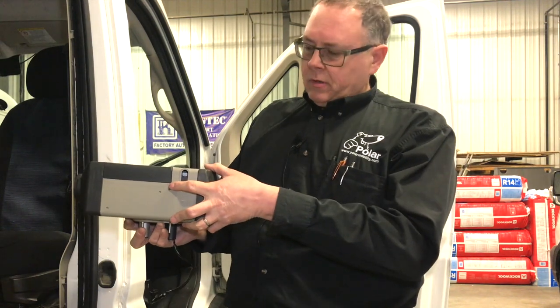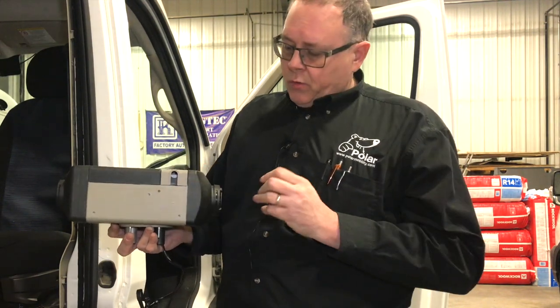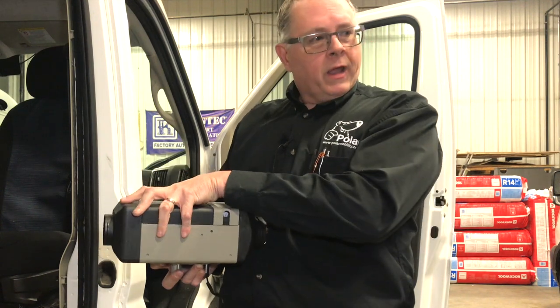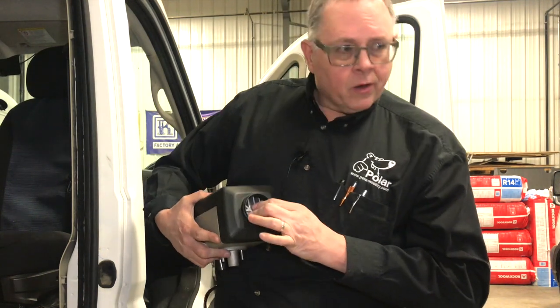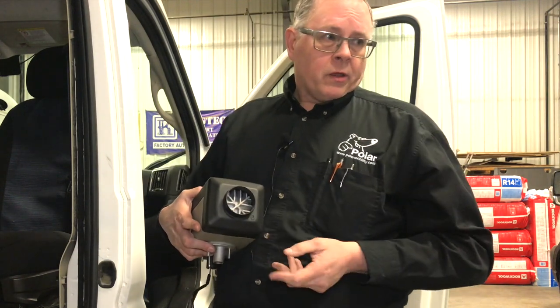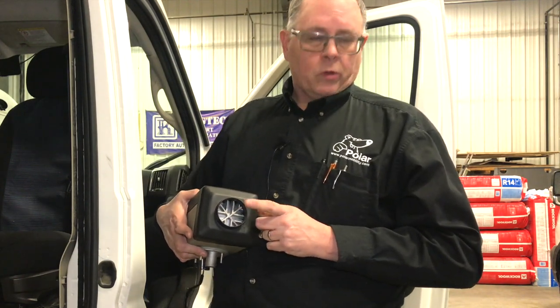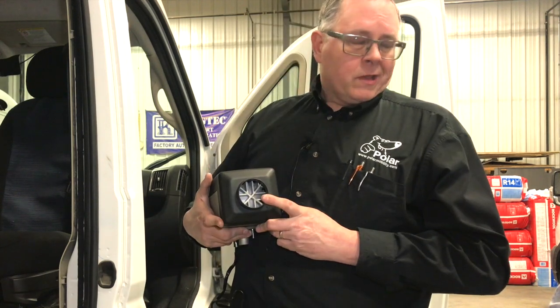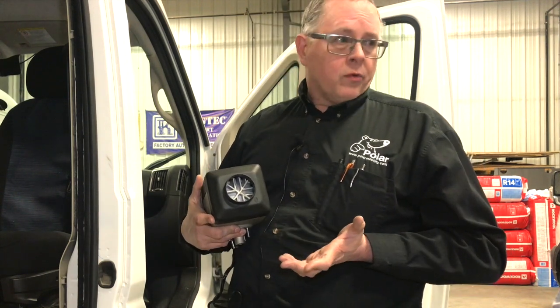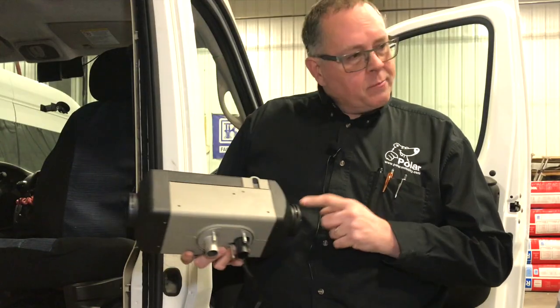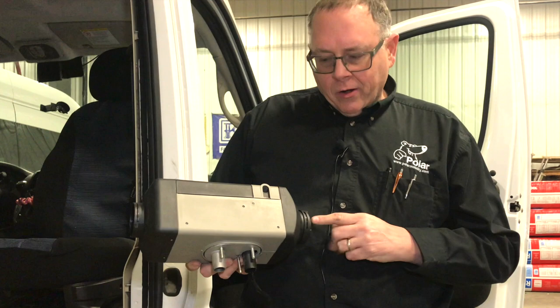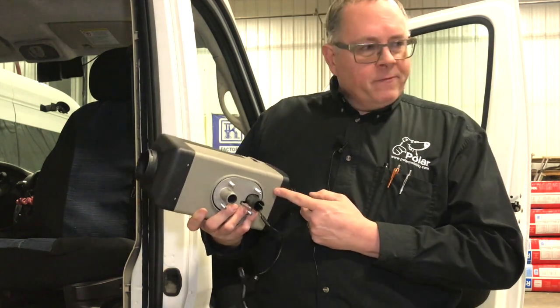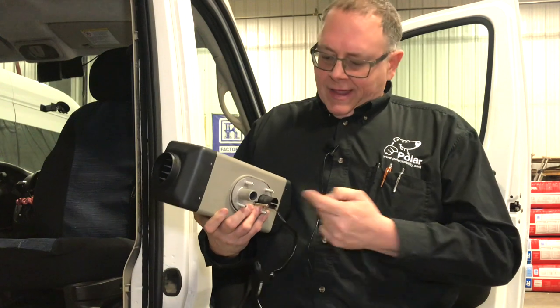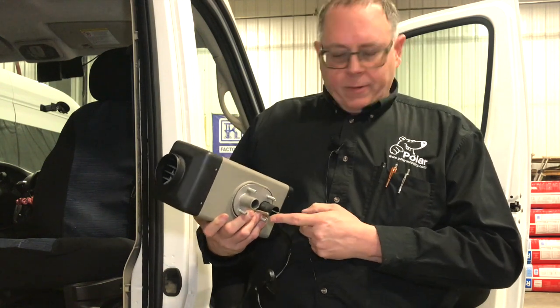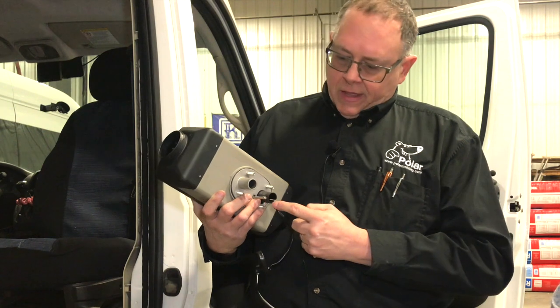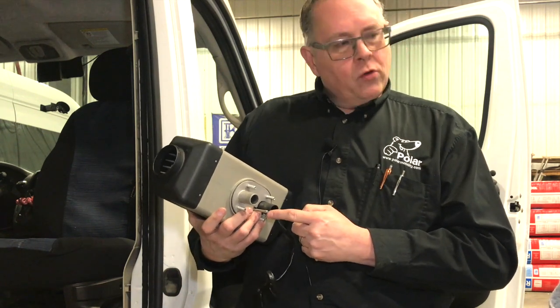There's a fan system, just like your house furnace, so it pulls the air in over a hot heat exchanger, and then you have your hot air that comes out this end. You have to be very careful never to put anything close to this outlet — it could potentially put out in the neighborhood of 200 degrees Fahrenheit hot air. At the same time the fan is pulling air across the heat exchanger, the same fan is also pulling combustion air inside the heater. The fuel pump is sending fuel through this little pipe into the heater, and the air and fuel mixture mix together.